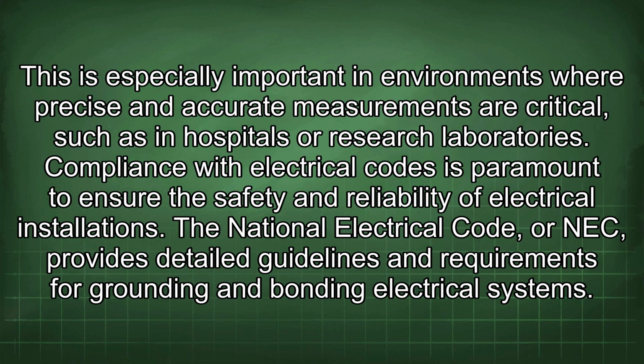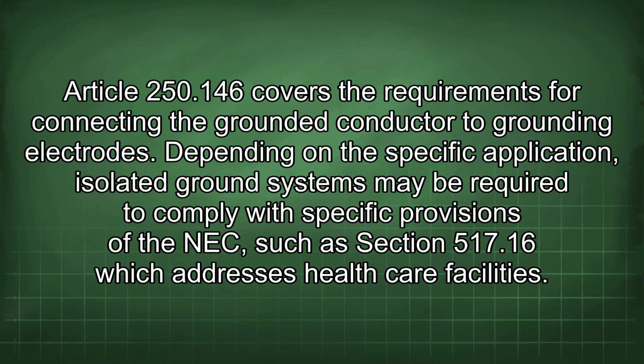Compliance with electrical codes is paramount to ensure the safety and reliability of electrical installations. The National Electrical Code, or NEC, provides detailed guidelines and requirements for grounding and bonding electrical systems. Article 250.146 covers the requirements for connecting the grounded conductor to grounding electrodes. Depending on the specific application, isolated ground systems may be required to comply with specific provisions of the NEC, such as Section 517.16, which addresses healthcare facilities.